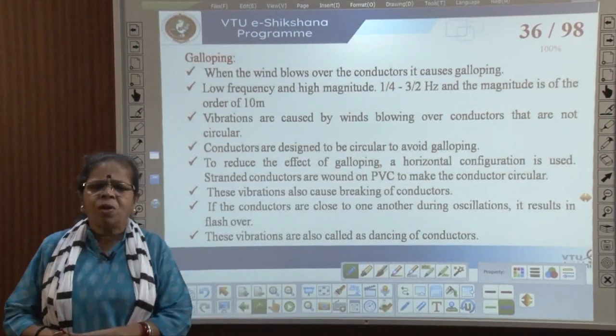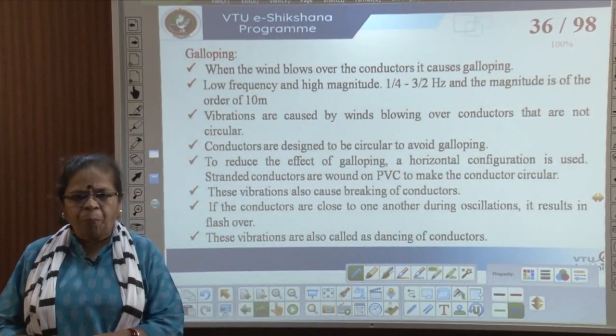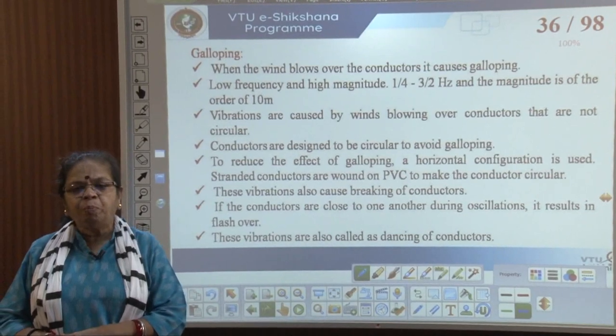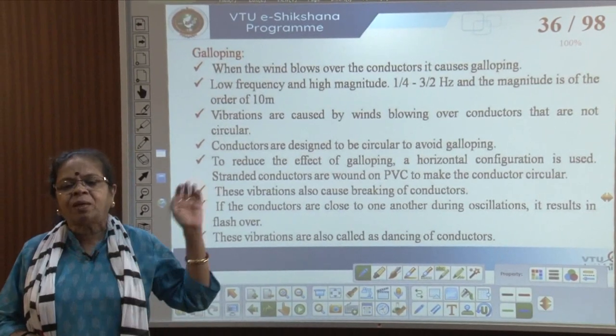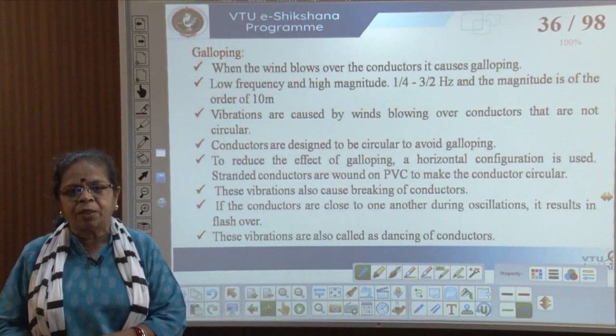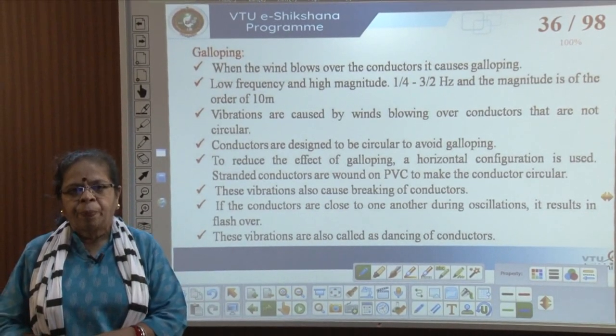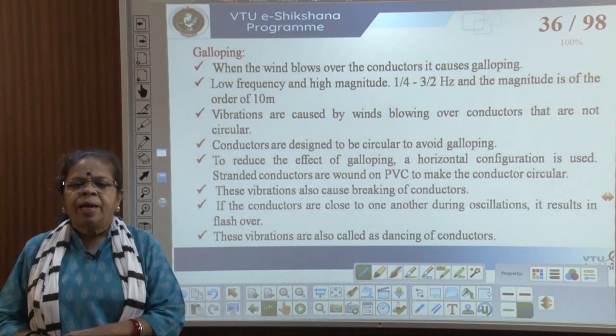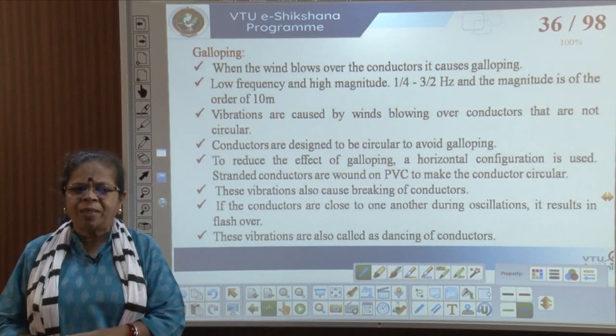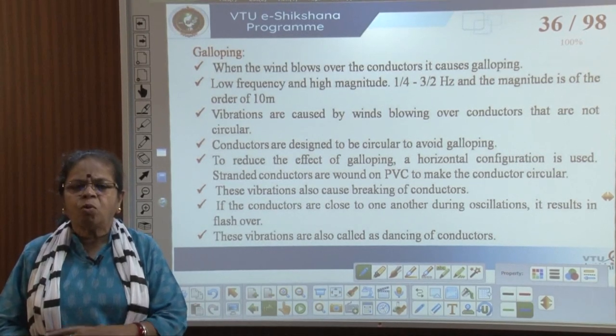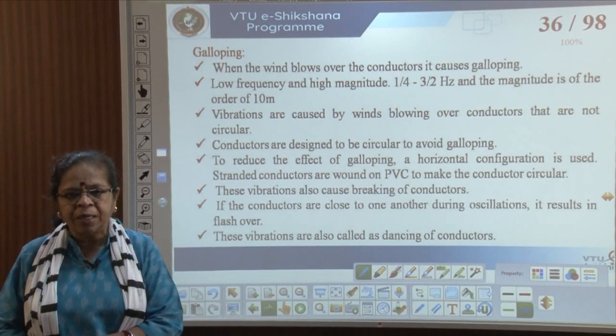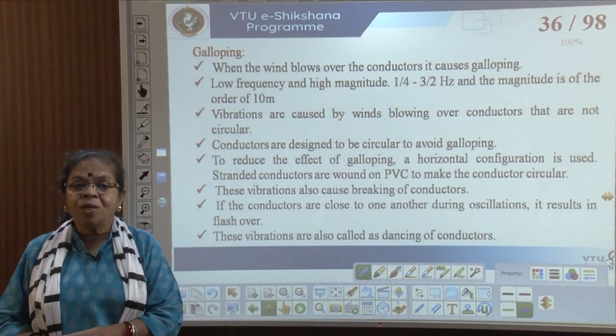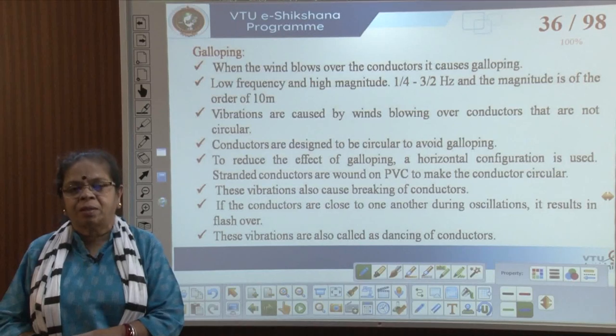Galloping occurs when the wind blows over the conductors. It is of low frequency — around one-fourth to one and a half hertz — and the magnitude is much higher, around 10 meters. So you get huge jumping of the conductors.